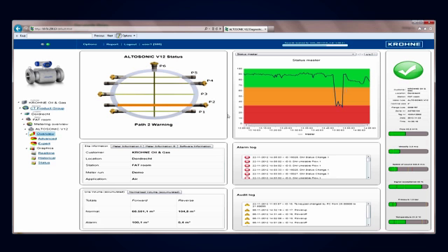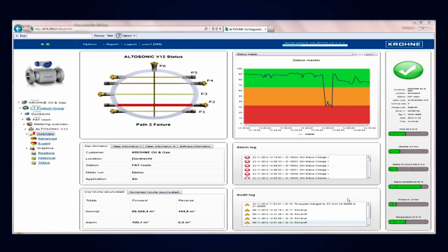There we get the warning on path 2. The flow meter is still within custody transfer accuracy. There is, however, a warning now on path 2. At this moment it's a warning, and in a few seconds this will become an error as the path is blocked by a piece of tape.